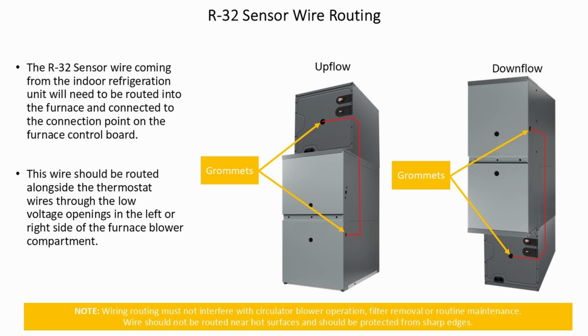Note: wire routing must not interfere with the circulation blower operation, filter removal, or routine maintenance. Wire should not be routed near hot surfaces and should be protected from sharp edges.